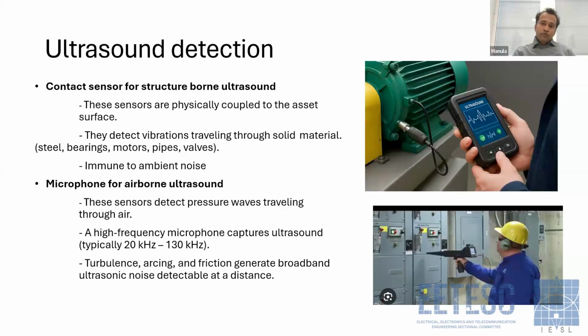As an example, if you want to measure the structure-borne ultrasound on a motor bearing, you would need to mount your ultrasound sensor on the bearing housing. Since we are mounting our sensor directly on the sound source, it is immune to ambient noise. It doesn't matter how loud the ambient environment is, because we are directly measuring on the sound source itself. So it is more or less like measuring vibration with our vibration meters.